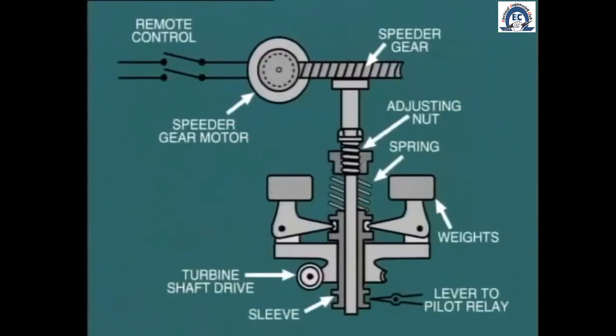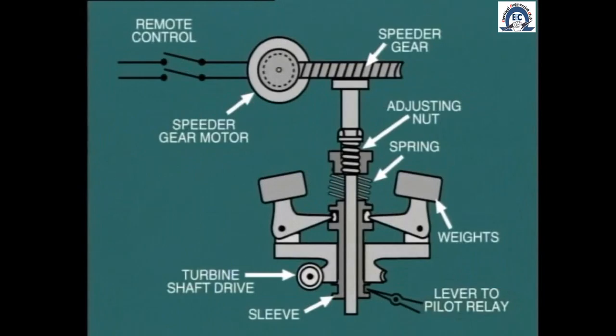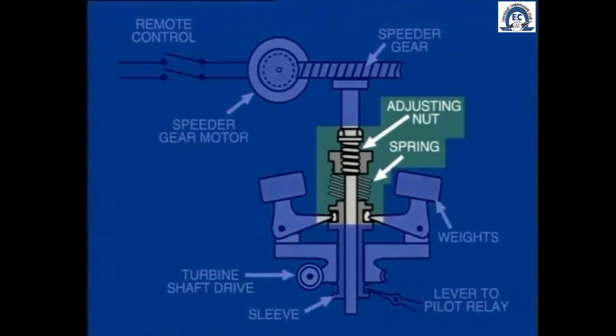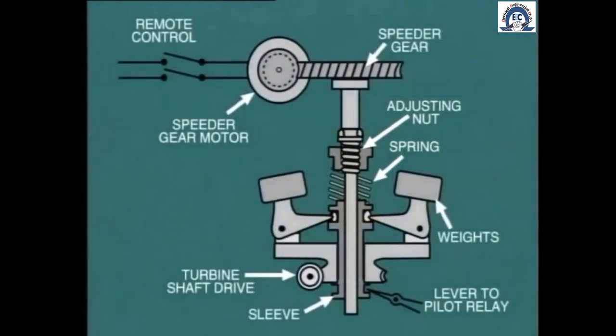Now let's take a closer look at the governor itself. This mechanical-type centrifugal governor is driven directly from the turbine shaft through a gear drive. As speed increases, the weights fly outward due to centrifugal force and lift the sleeve against the compression spring. The sleeve itself is connected to the pilot relay, which in turn adjusts the control valve through the hydraulic servo mechanism. We can adjust the set point of the governor by adjusting the compression on the spring. The adjusting nut moves up or down according to rotation of the screw thread. This action can be performed manually at the turbine.